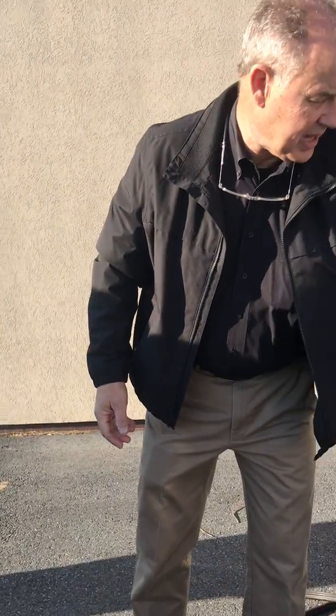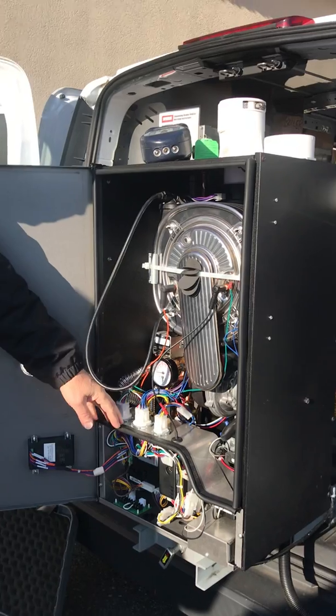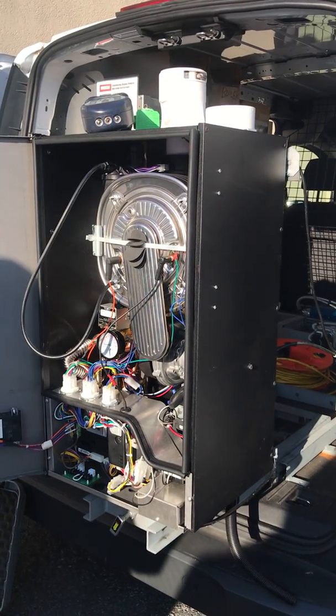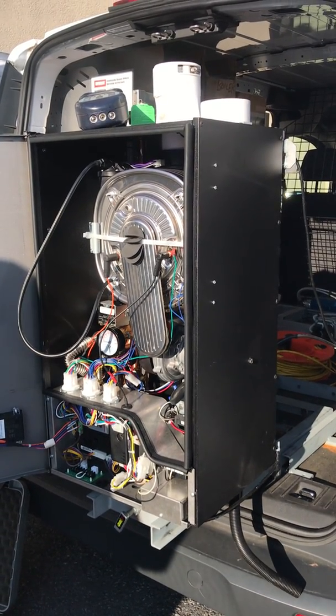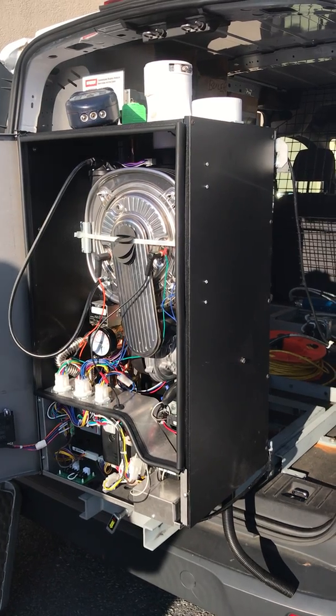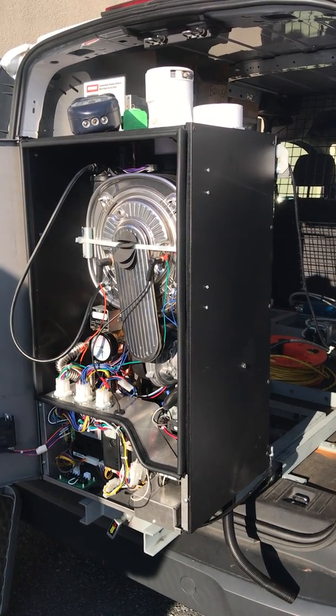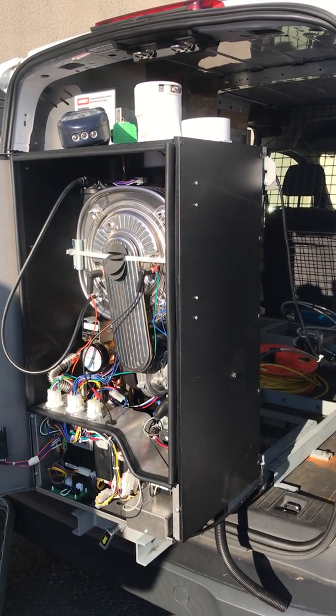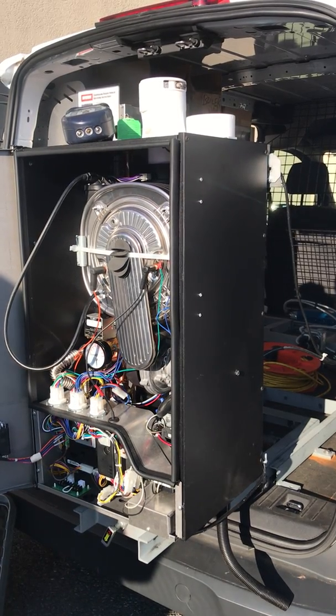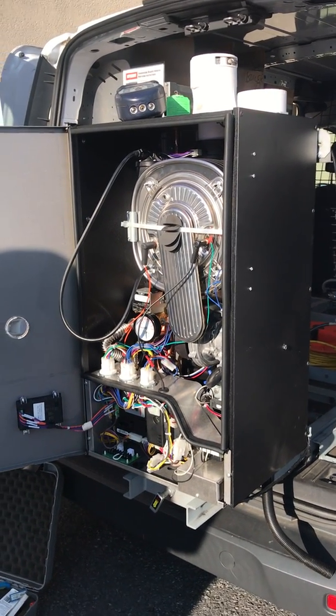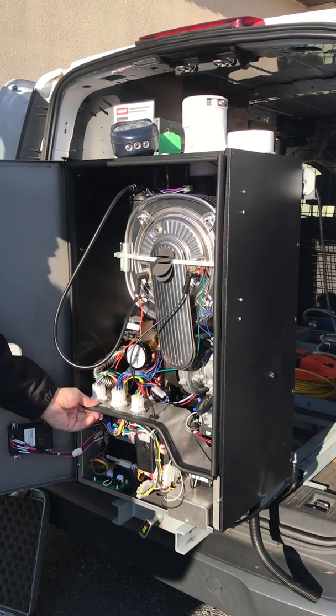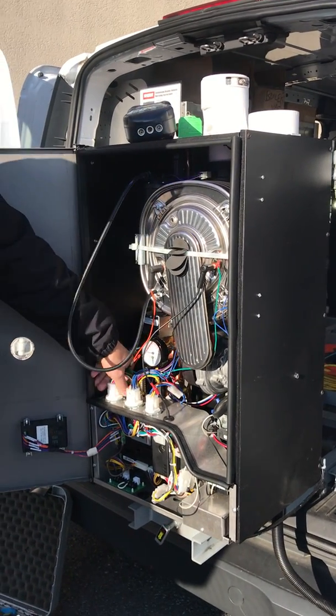And then when they put the flanges on, you can kind of see the flange. It looks like it's really tough, but when I pull this apart, it's not that bad getting in. But when you get to the circulator flanges, they actually put a grease on there that they slip and slide around. It was a little bit of a pain. So you're saying if we take that control box, the bottom box, out, you can get to that circulator without a problem? Yeah.